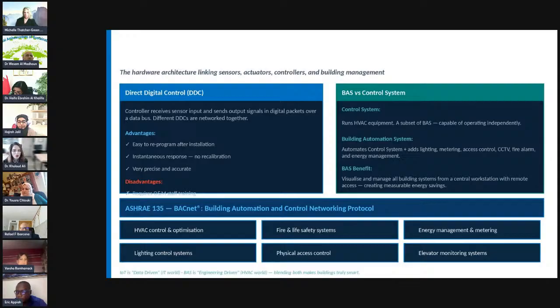The Control System runs the HVAC equipment, a subset of the BAS, capable of operating independently. The BAS itself automates control systems and adds lighting, metering, access control, CCTV, fire alarm, and energy management. The benefit is it visualizes and manages all building systems from a central workstation with remote access, creating measurable energy savings.